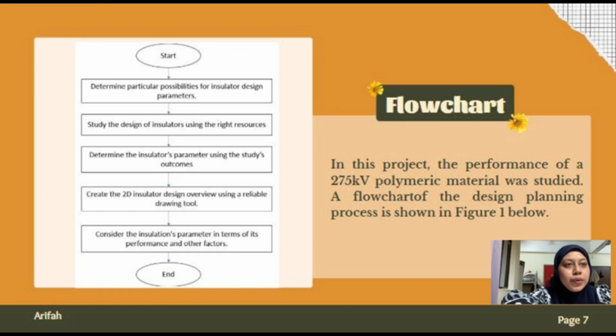So I will continue with my part, which is the design planning. For the design planning, our project decided to use 275 kV polymeric material. So this is our flow chart. After deciding the insulator that will be used, we need to determine the amount of load that will pass through it. So for our project, the specification is 275 kV.